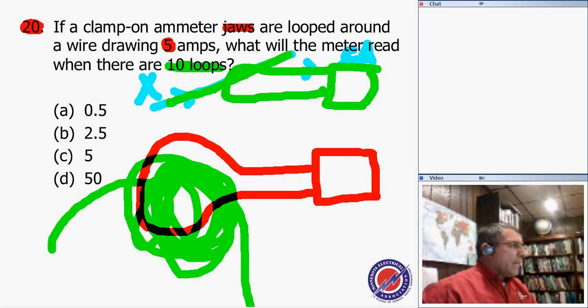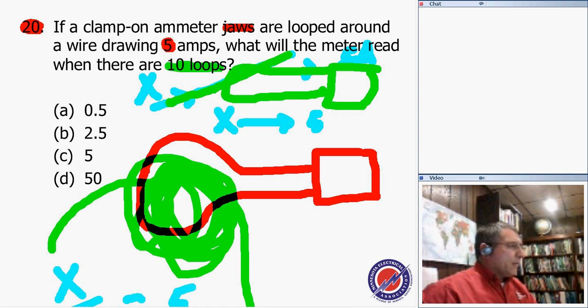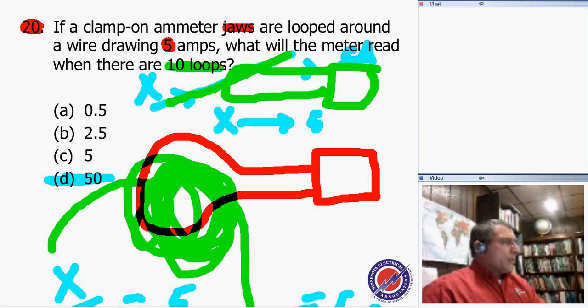I'm going to make it complicated. Suppose X is the current. If X current can give you 5 amps, okay? If you loop it, it becomes X divided by 10 amps, right? And the X current that will be read is 5 times 10, which is 50 if I did my math right. So 50 amps. The meter is going to read 50 amps. But in reality, guys, we don't use it this way.